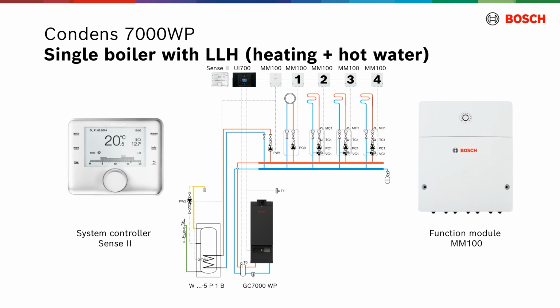Cylinder charging circuit with the cylinder primary pump and circulation pump are connected to the function module MM100 with the coding switch, position 9. This allows to control the pumps in the circuit, set up time program for thermal disinfection and circulation, and the domestic hot water temperature via system controller Sense2.